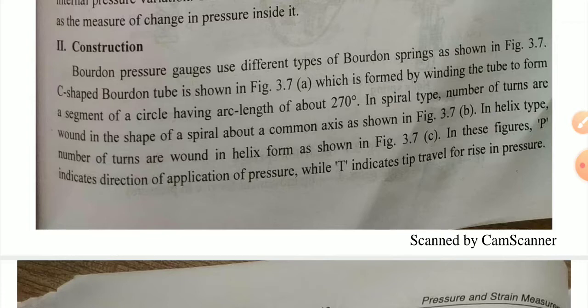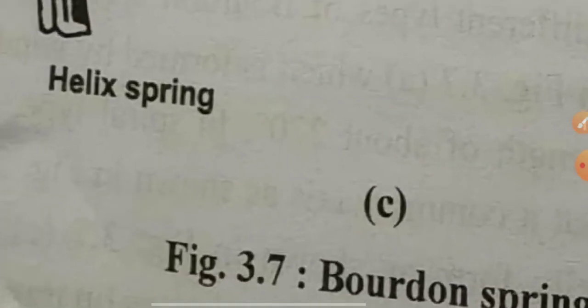For the Bourdon pressure gauge, figure 3.7 is the C-shaped Bourdon tube, which is formed by winding the tube in the form of a segment of a circle having an arc length of about 270 degrees, in a spiral type. The number of turns are wound in the shape of a spiral about the common axis as shown in the figure, and the helix type is also shown. Okay, there are different types of figures. I have sent the PDF in the group, make sure to look at it once.